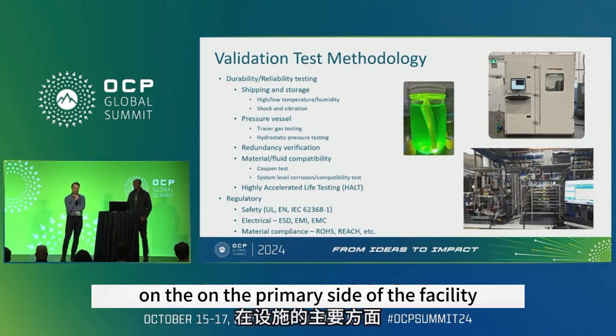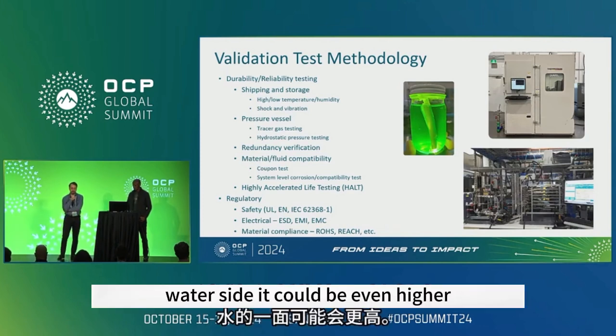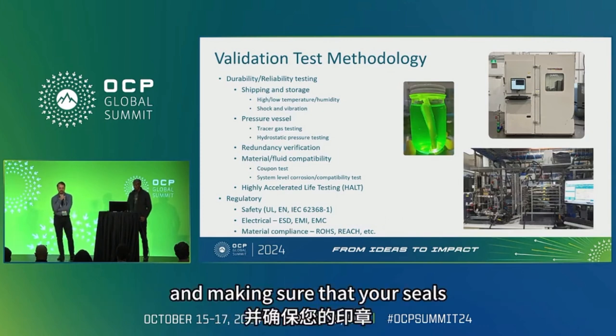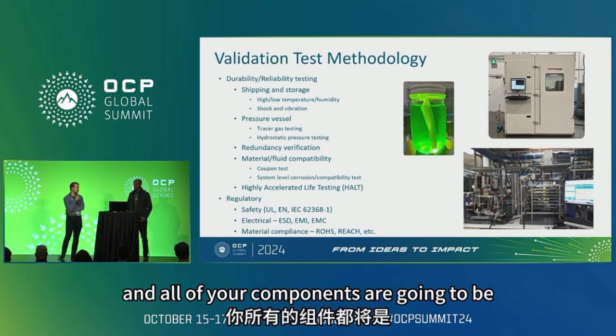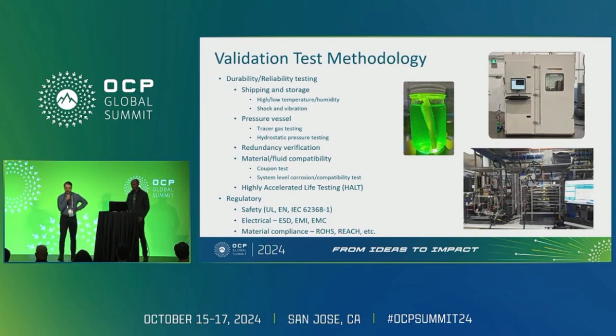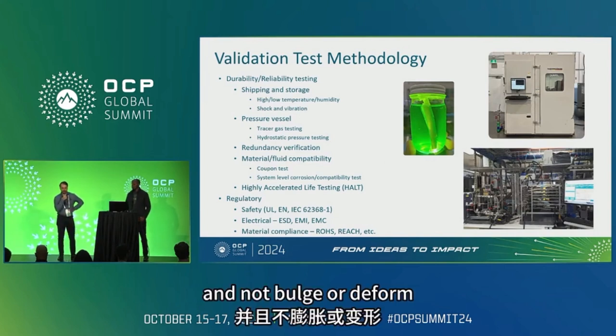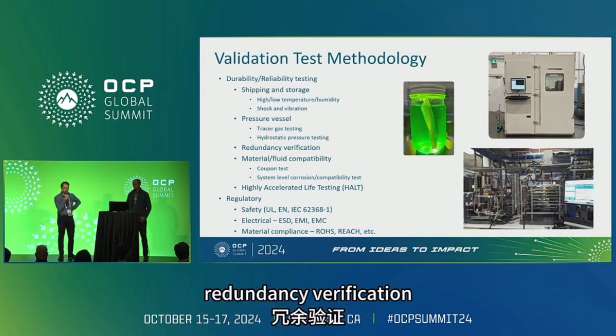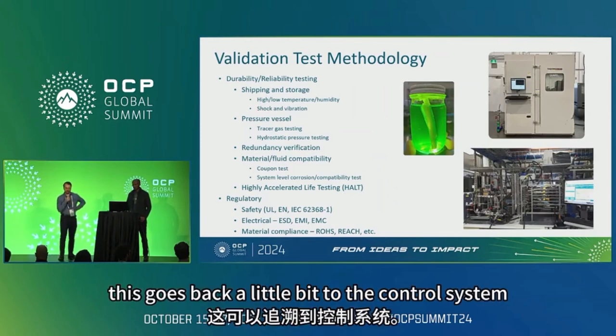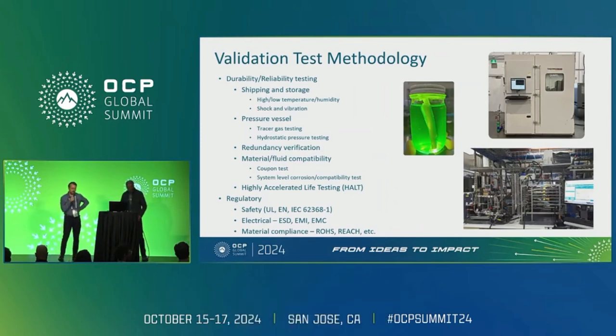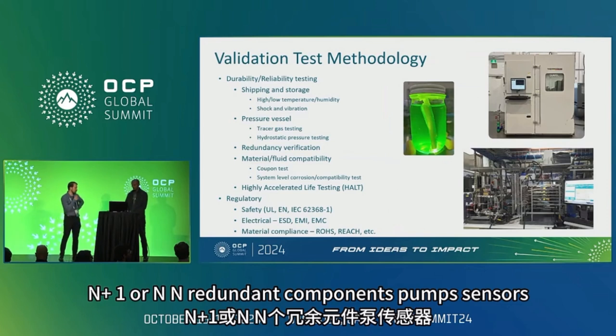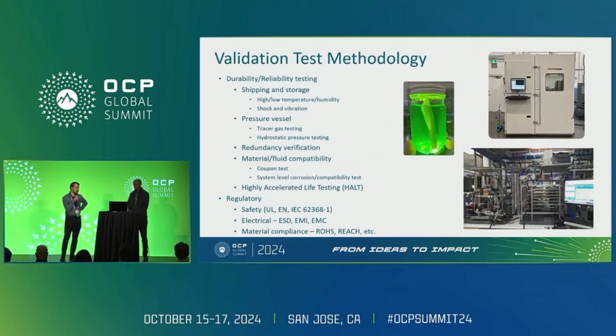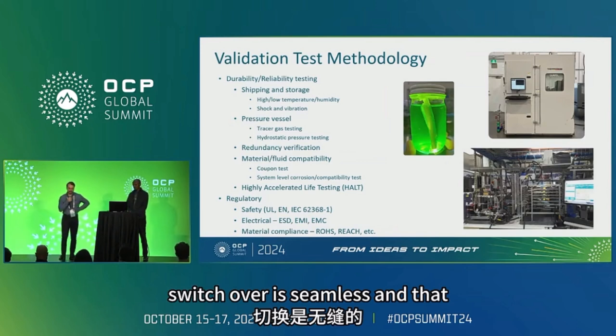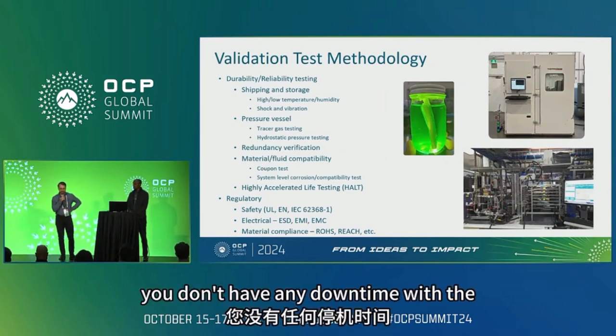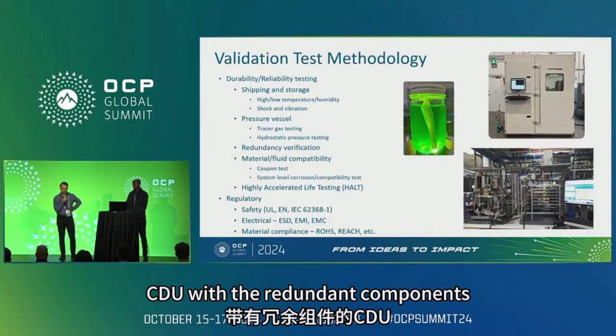On the primary side or the facility water side, it could be even higher. And making sure that your seals and all of your components are going to be able to withstand and not bulge or deform. Redundancy verification, again, this goes back a little bit to the control system, but a lot of CDUs have N+1 or N+N redundant components, pumps, sensors, so making sure that switchover is seamless and that you don't have any downtime with the CDU with the redundant components.